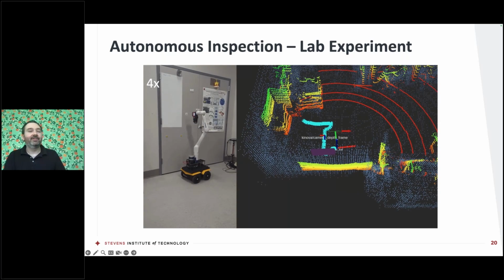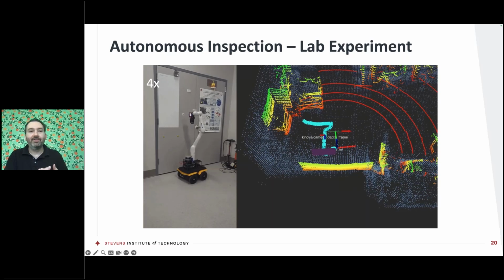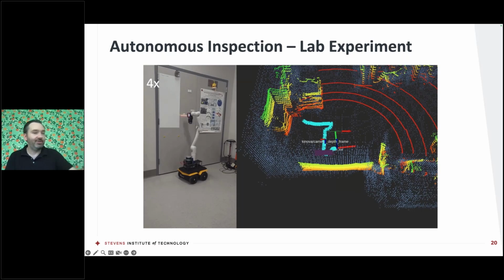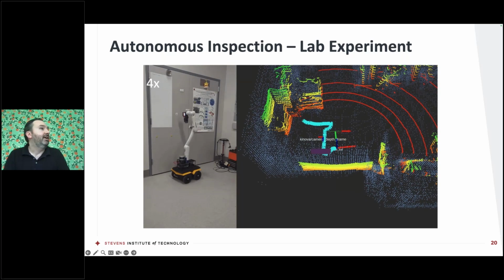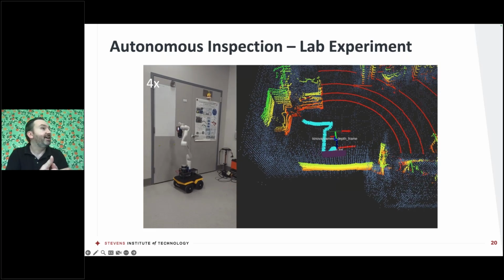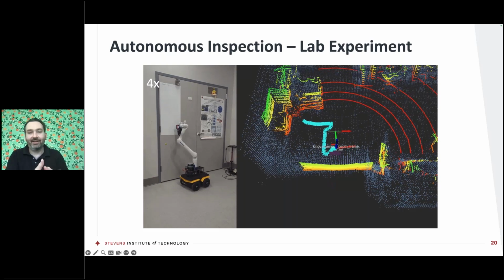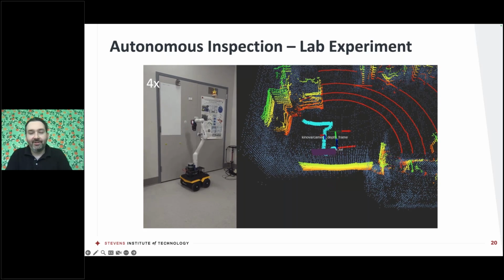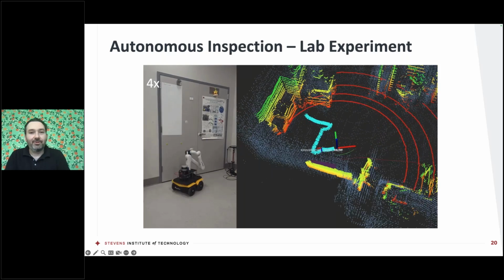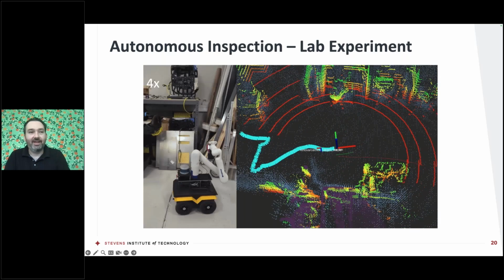Given some knowledge in advance of where the vents are to take acoustic measurements, it reaches to that location and takes an acoustic sample. It also makes physical contact with the door to collect a TEV measurement, which you see happening right there - that was the physical contact. It uses its onboard torque sensors to ensure the contact was made.